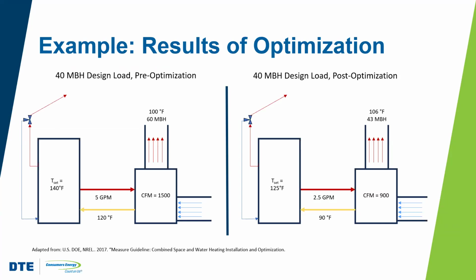And so here is an example of what can be achieved with system optimization. This system happens to be rated for potable use, so it's mixing domestic and space water heating. In this particular case, the design load was 40 MBH, but the initial system was set up to give out as much heat as possible with the air handler at the highest speed. Going through that iterative optimization process, we were able to lower the GPM and provide about a 10% efficiency gain for the system.